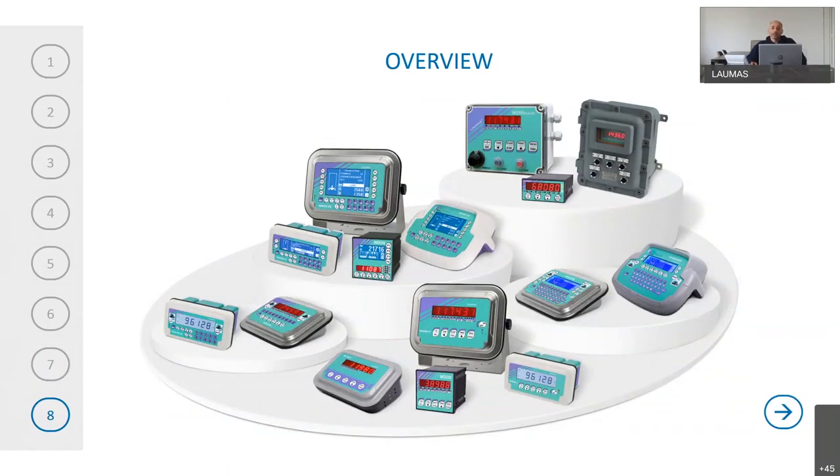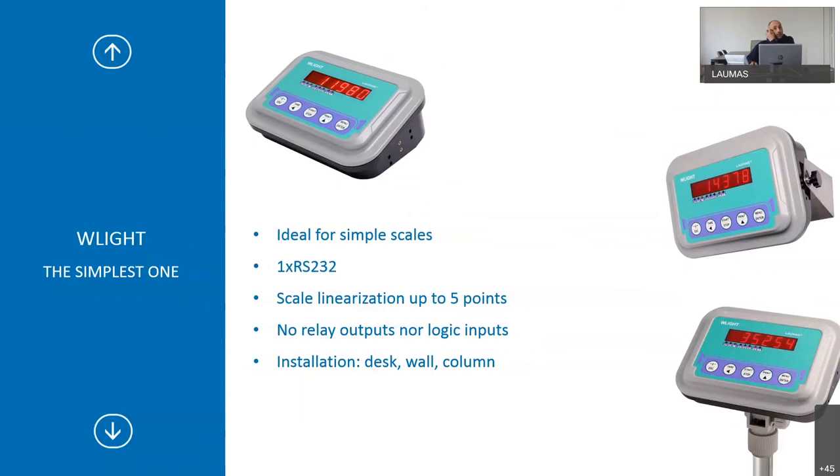Let's look at individual indicators and the differences between them. WLight is the simplest and is mainly used in small scales when you want a low-cost indicator with basic features. It has only one serial port RS-232, scale linearization up to five points, no relay outputs and no logic inputs. Installation can be on desk, wall or column.